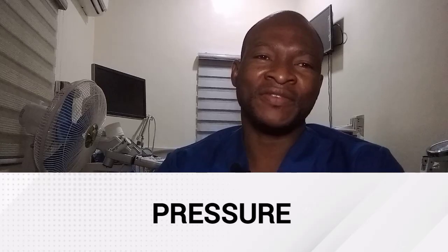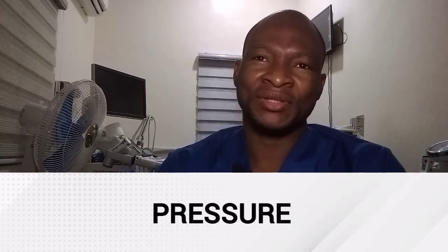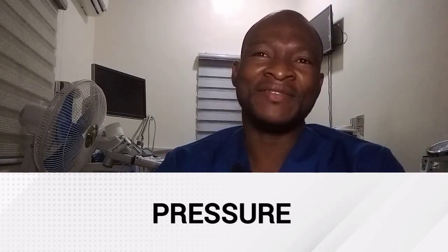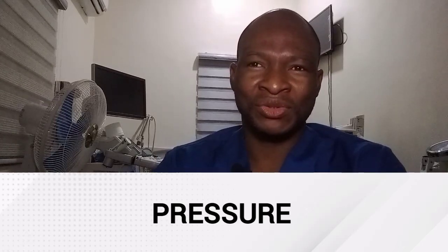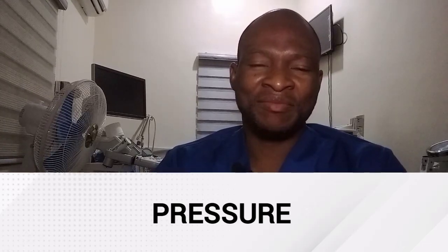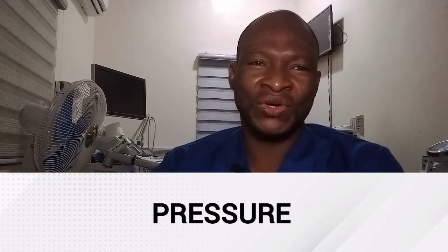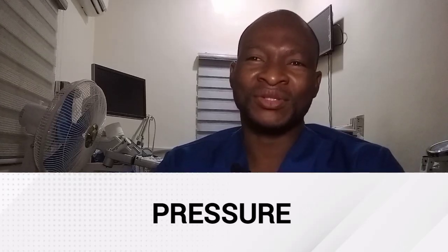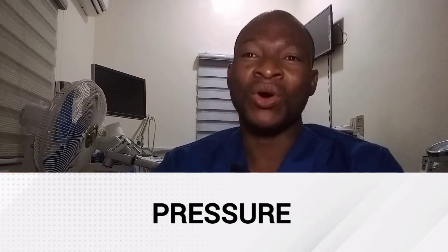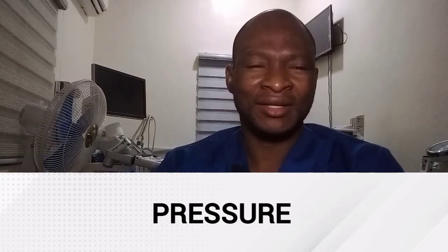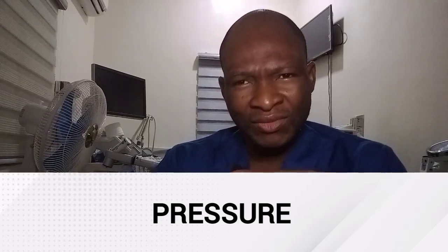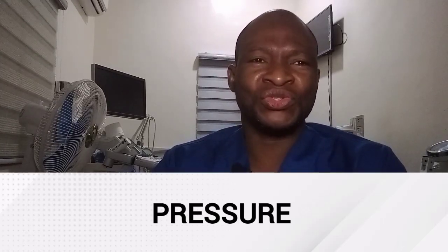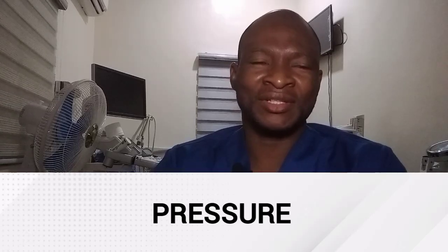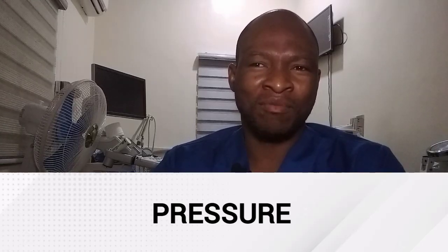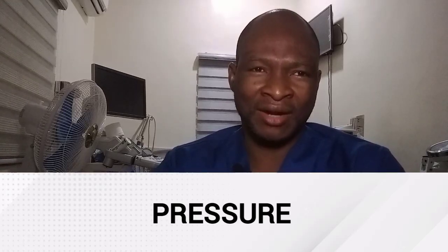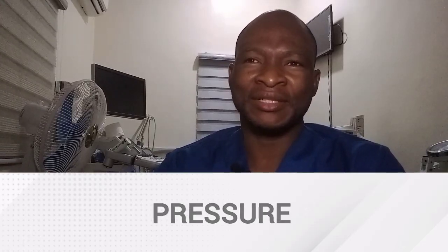Beam width also affects pressure. So pressure and intensity are inversely proportional to area. The smaller the beam width, the greater the pressure and intensity. All the factors which influence beam width will also affect pressure and intensity. For example, a focused beam will produce the highest intensity between the transducer face and the focal point. The focal point is actually the narrowest beam diameter.